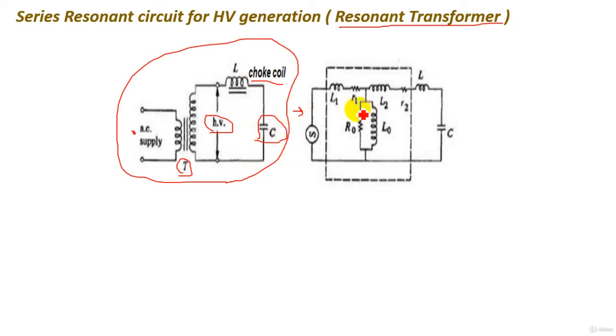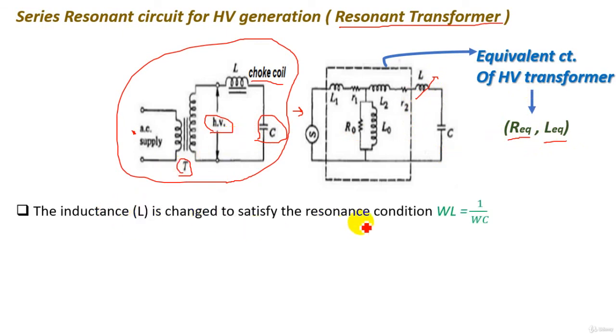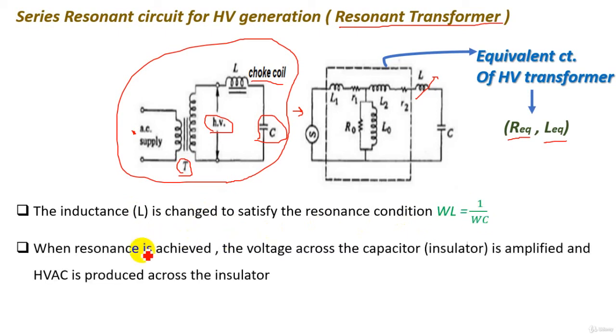The circuit has a supply, and the rectangle represents the equivalent circuit of the high-voltage transformer, which can be represented as an equivalent resistance and equivalent inductor. The variable choke coil is adjusted to make resonance. The inductance L is changed to satisfy the resonance condition ωL equals 1/ωC. When resonance is achieved, the voltage across the capacitor — the insulator — is amplified, and high-voltage AC is produced across the insulator.